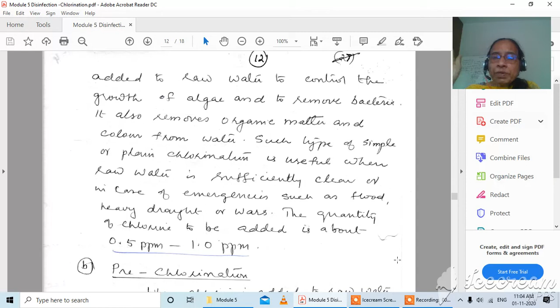On all these three conditions we are recommending plain chlorination, and the quantity of chlorine to be added is about 0.5 ppm to 1 ppm. So that is the recommended dosage for plain chlorination. Remember, it is without any other treatment. When you are utilizing chlorination or disinfection as the only treatment method, then we are calling it plain chlorination.